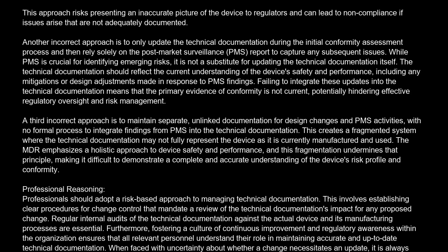Another incorrect approach is to only update the technical documentation during the initial conformity assessment process and then rely solely on the post-market surveillance, PMS, report to capture any subsequent issues. While PMS is crucial for identifying emerging risks, it is not a substitute for updating the technical documentation itself. The technical documentation should reflect the current understanding of the device's safety and performance, including any mitigations or design adjustments made in response to PMS findings.